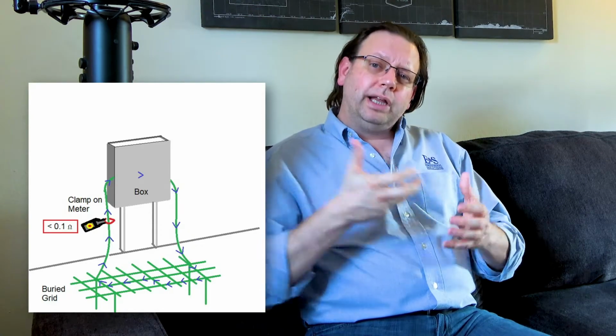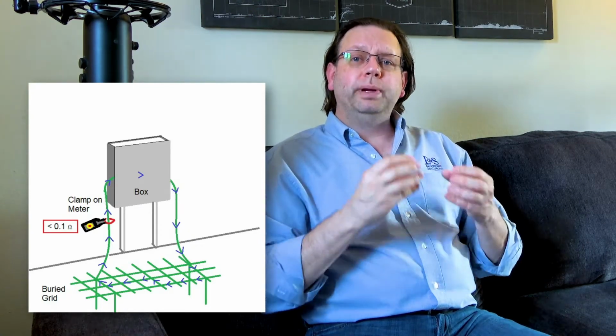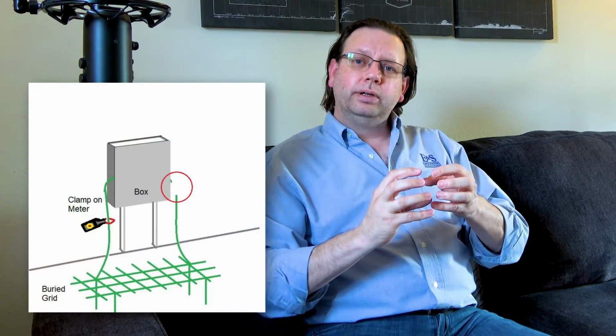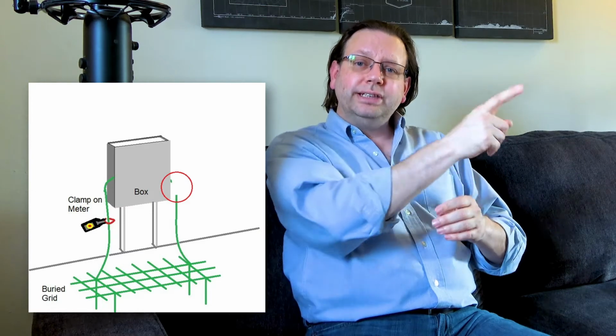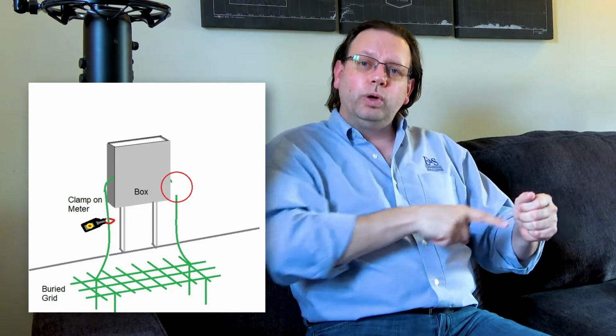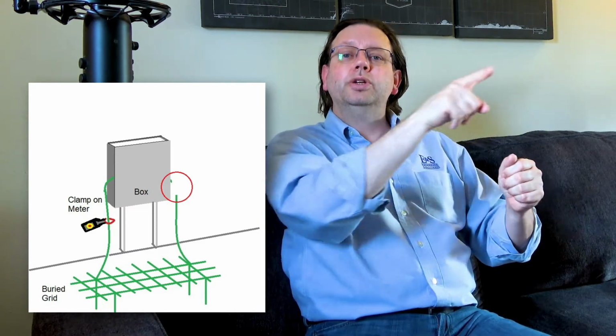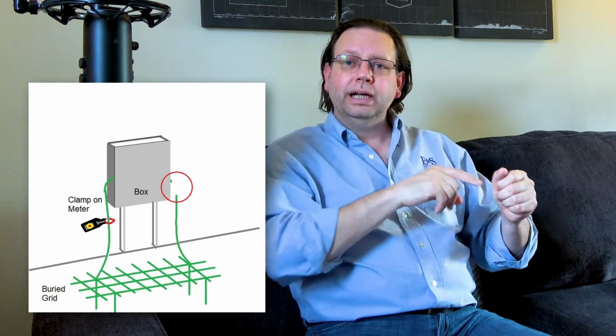Right. By clamping onto that wire, we are expecting, again, a very low reading. That low reading will tell us that we have a nice continuous loop around that equipment, a local area continuity check. Right. Now, let's say, for example, one of those ground wires was broken and had fallen off.